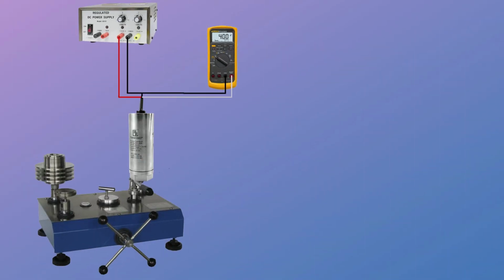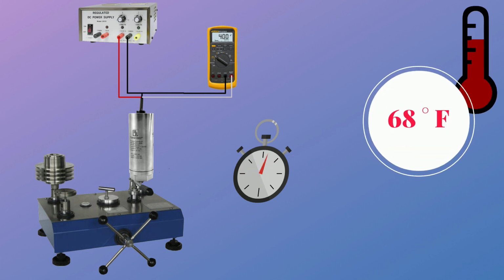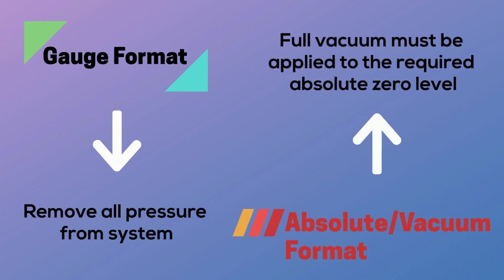Next, power up the system and wait typically 10 minutes for the electronics to warm up and the system to settle. Calibration for standard transmitters is typically performed at room temperature or 68 degrees Fahrenheit. For this example, we are using a 0 to 500 psi device. If it's a gauge format, remove all pressure from the system to obtain a 0 psi pressure. If it's absolute or vacuum format, an absolute zero pressure must be obtained or a full vacuum to the required zero level.